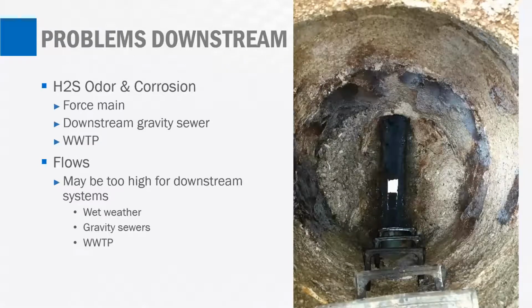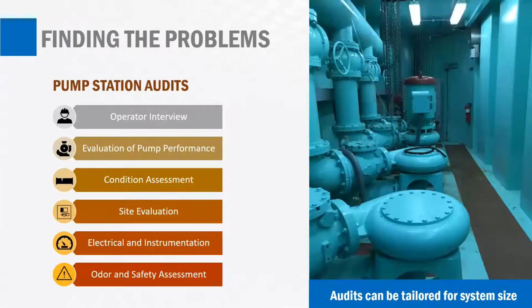Flows. What's happening downstream with your flows? Pump stations could be sized too high. I think a lot of us know that state requirements as far as the amount of flows that go through pump stations are relatively conservative. And is your pumping system sized too high for the wastewater that's coming to it? That could be a problem if you're experiencing wet weather. And what happens downstream, you could cause SSOs if your pumps are pumping too high. So there's lots of different problems that you can find that are associated with your pump station, your wastewater pumping systems. And again, it's important to understand that force mains are really a part of that overall system.